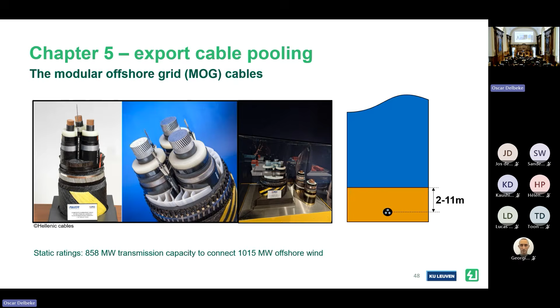And the real limit on how much power this cable can transfer is set by the conductor temperature. Now, the conductor temperature, these big cores of aluminium, if they cross 90 degrees, then the insulation around them starts to degrade. So theoretically, we could push a lot of power through the cables until this temperature is reached, but then we have to slow down and stop. So we can operate above this static rating as long as we respect the temperature.